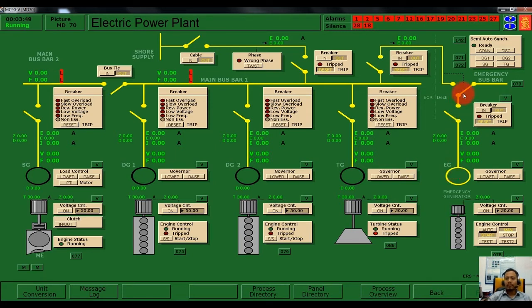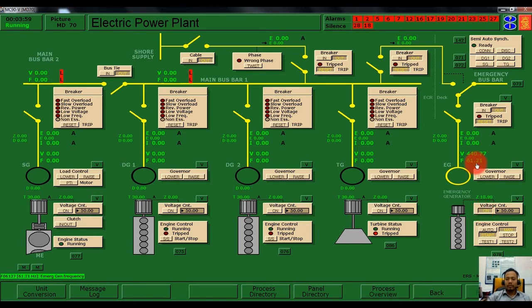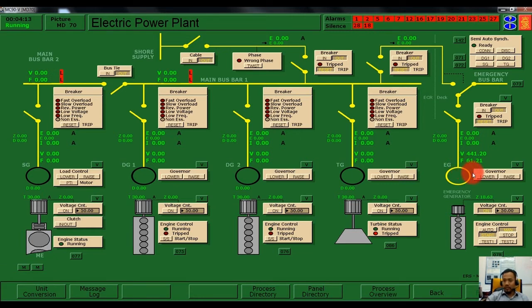In order to lower or raise the voltage, we need to switch on the voltage controller. After switching on the voltage controller, we can adjust the voltage or the frequency — whether we want to raise or lower it. Currently the voltage is 441 volts; we want to lower the voltage to 440 volts and frequency to 60 hertz.